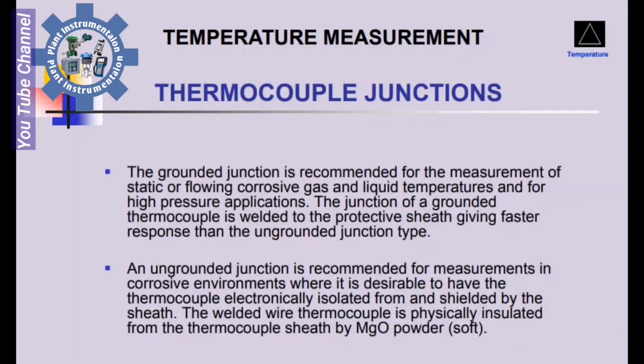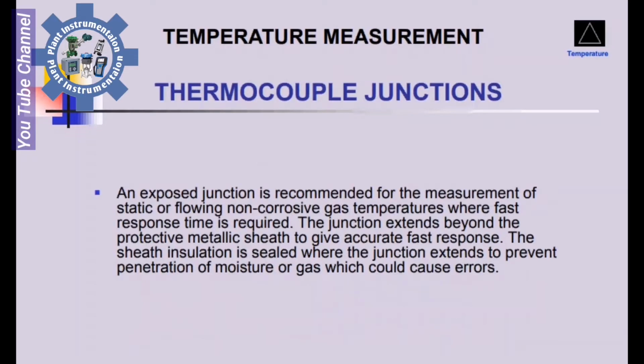The welded wire thermocouple is physically insulated from the thermocouple sheath by magnesium powder. An exposed junction is recommended for the measurement of static or flowing non-corrosive gas temperature where fast response time is required. The junction extends beyond the protective metallic sheath to give accurate, fast response. The sheath insulation is sealed where the junction extends to prevent penetration of moisture or gas which could cause errors.